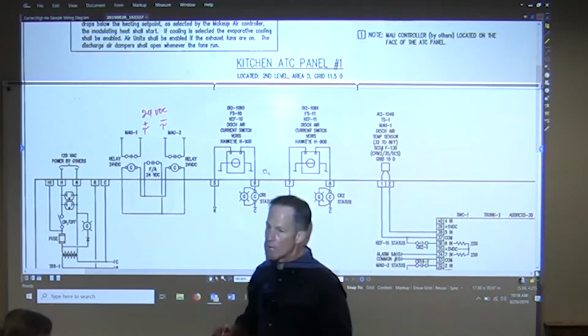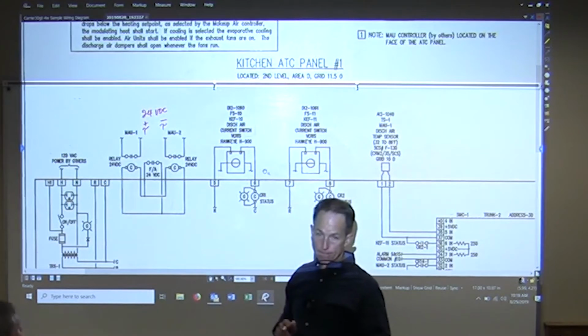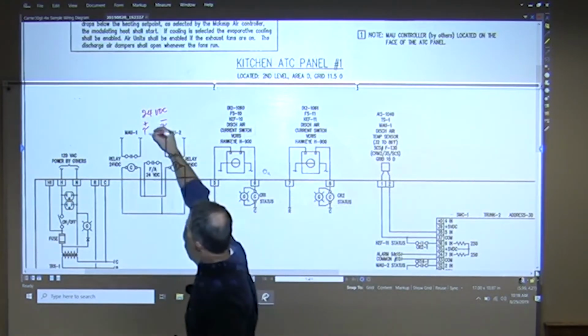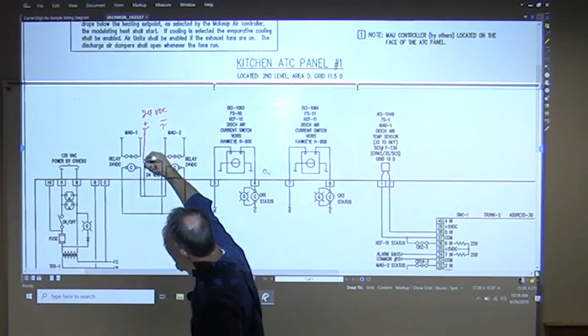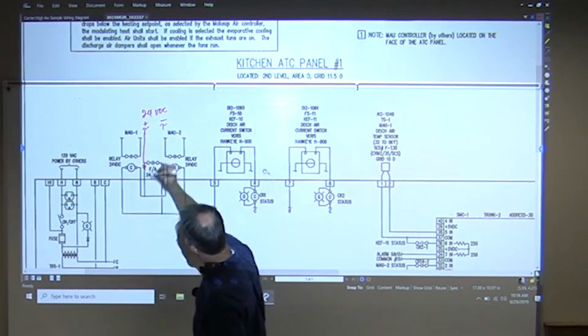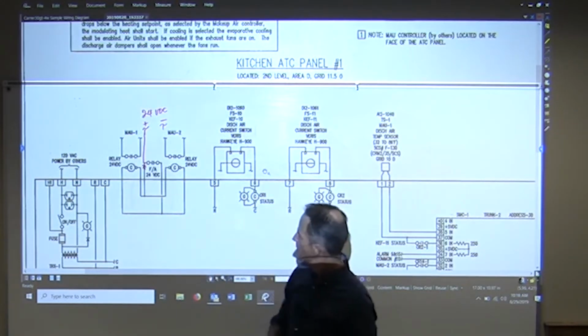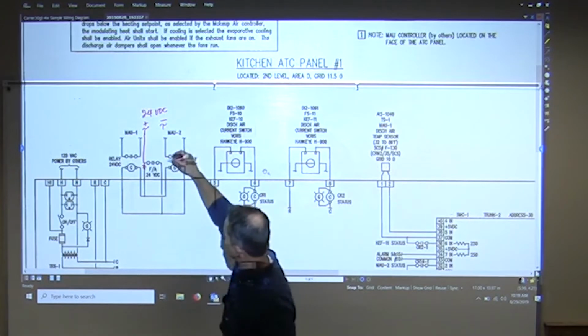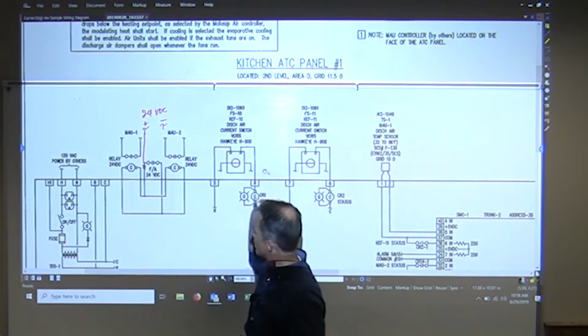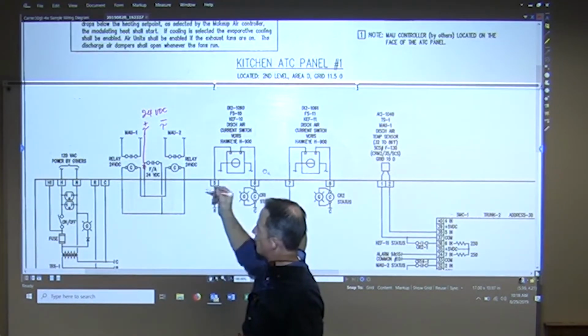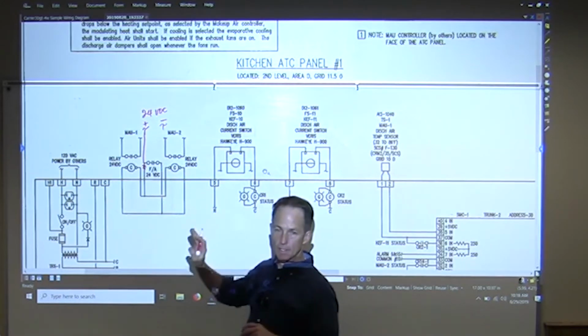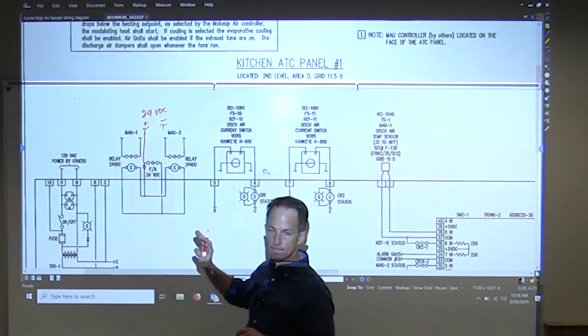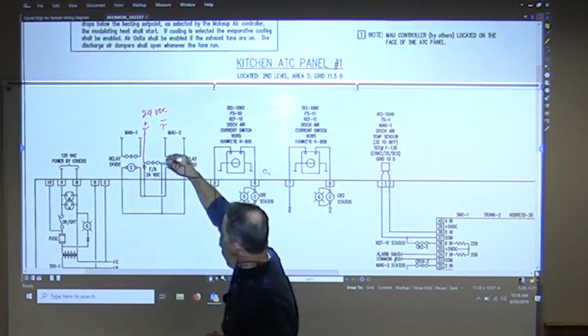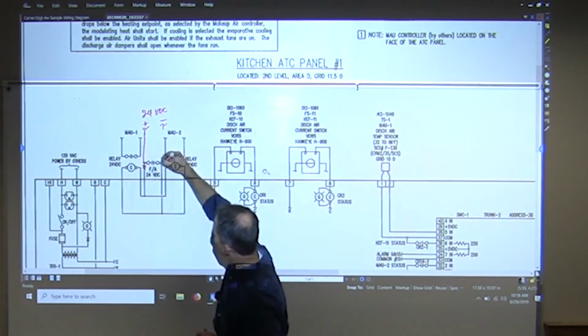Matt, go ahead, give us a shot. I'm going to assume we still want that contact in there, so go to the left side of the contact and separate the wire from the contact and go up. So we'll get rid of that wire right there. How's that? And then go off to the right side of that coil that's right next to it. Or probably should have got rid of the other side of that contact. Either way works. What we're doing is we're putting the power in series with the contact. Yeah. So we basically bring power into there.